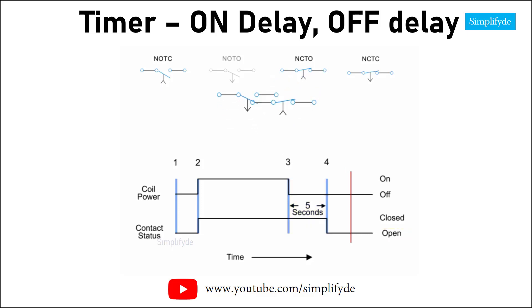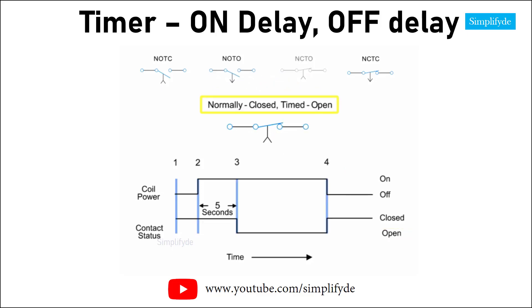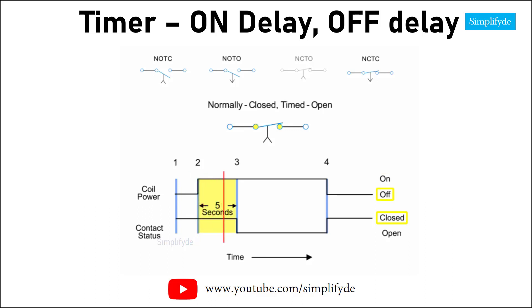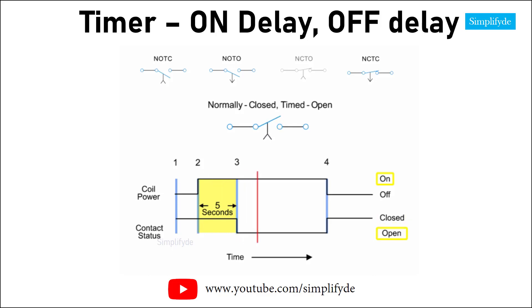Next, we have the normally closed timed open contact. This type of contact is normally closed when the coil is unpowered or de-energized. The contact is opened with the application of power to the relay coil, but only after the coil has been continuously powered for the specified amount of time — in this case, five seconds. Thus, the contacts open five seconds after the coil is energized, and close immediately when the coil is de-energized.